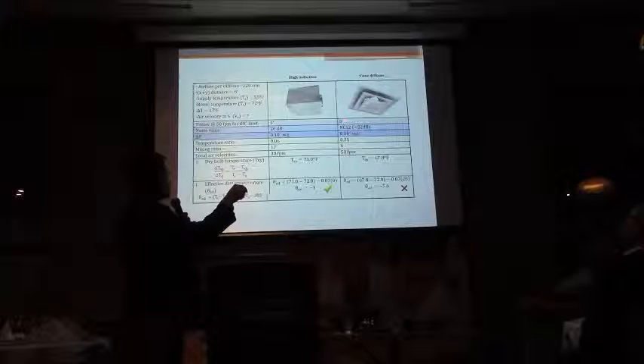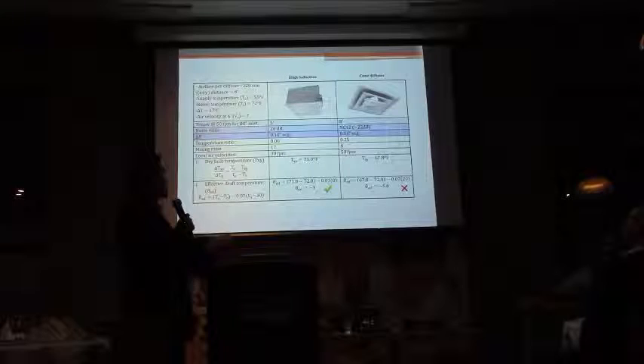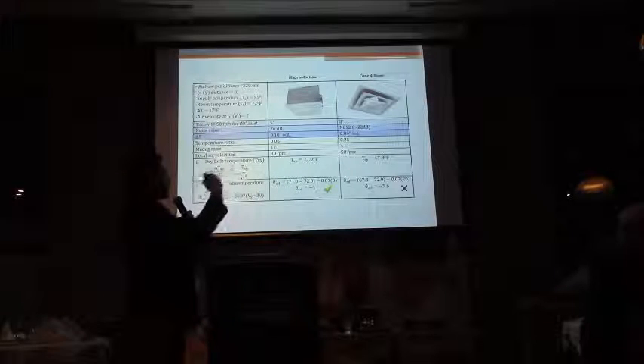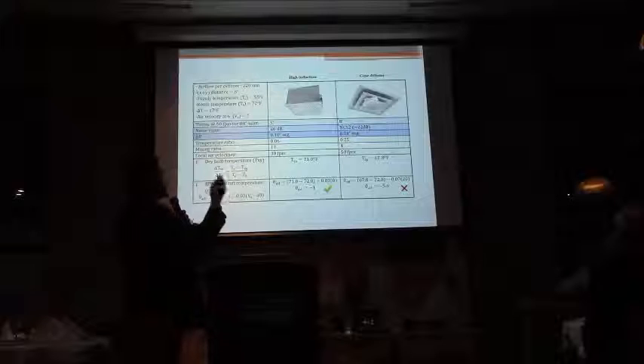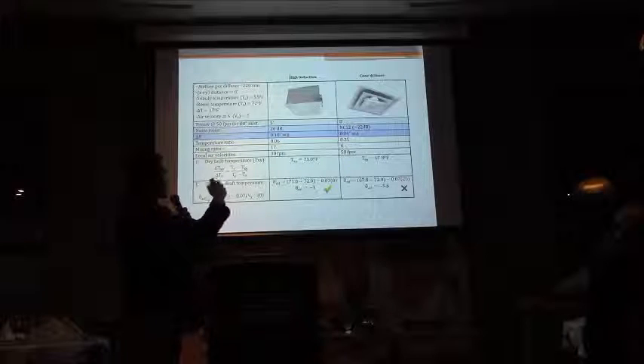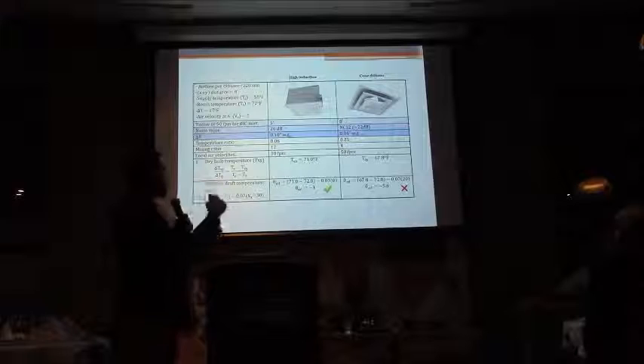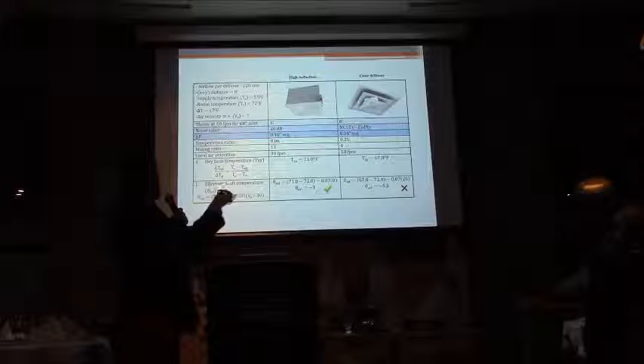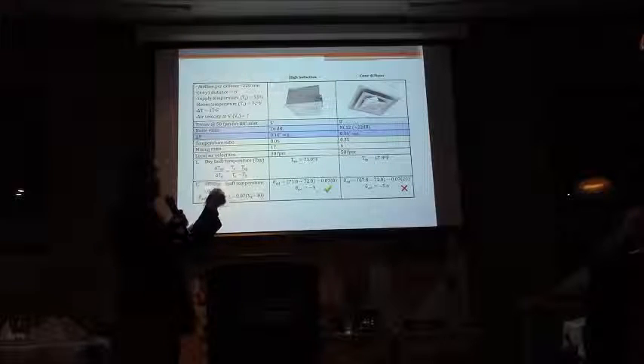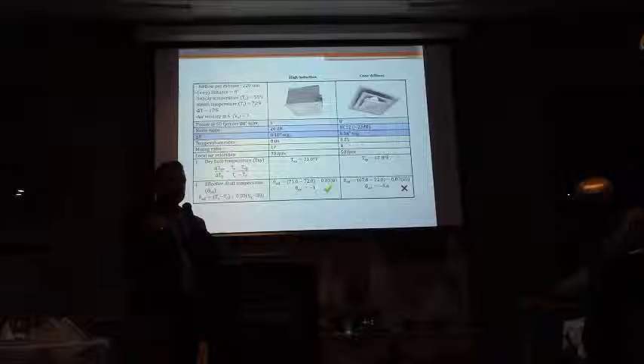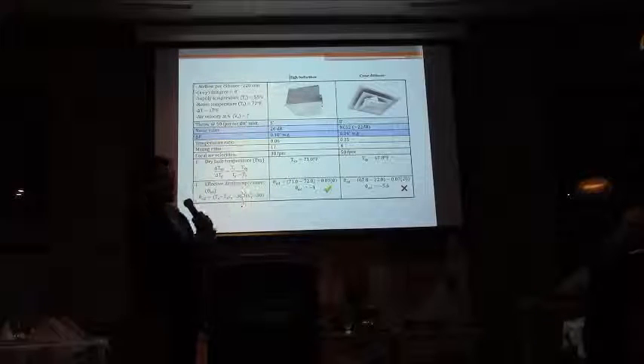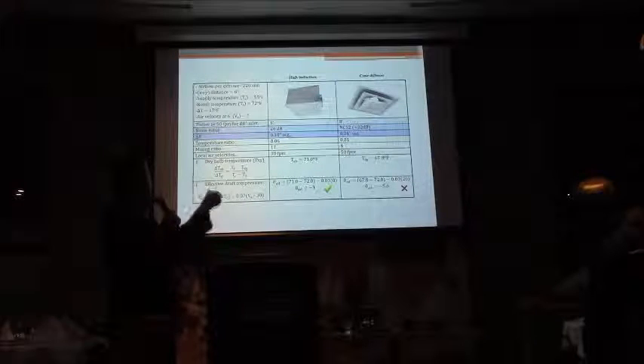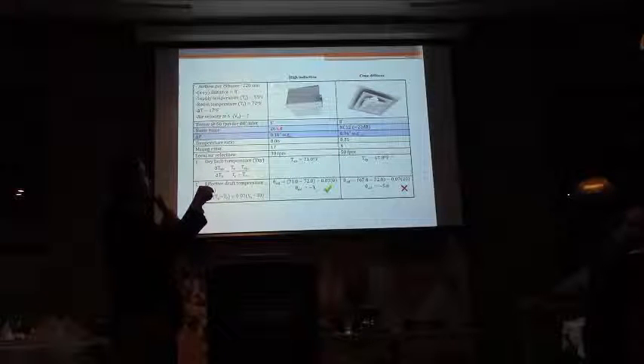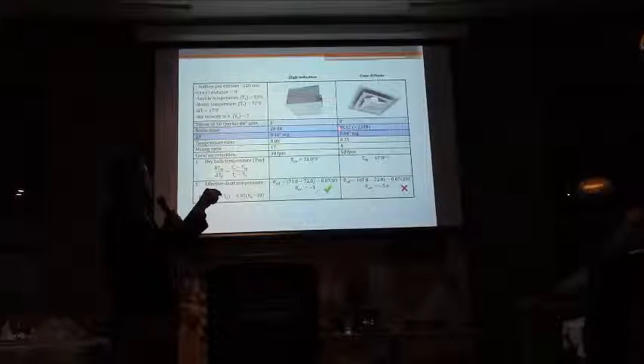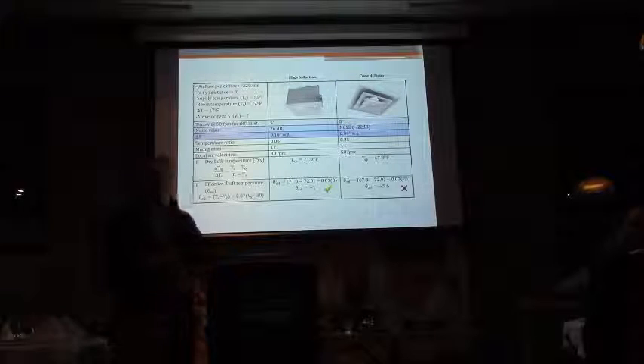And the values in blue are all the catalog values. So the cone diffuser is manufacturer B, and high induction is manufacturer A. And I took all their throw, noise values, and static pressure losses from their respective catalogs. So the noise values, if you notice, first thing, the throw of the high induction is much shorter than that of the cone diffuser. The second thing you might notice is that the noise value is 26 decibels here, while the cone diffuser is at NC12, which is close to 22 dBA.